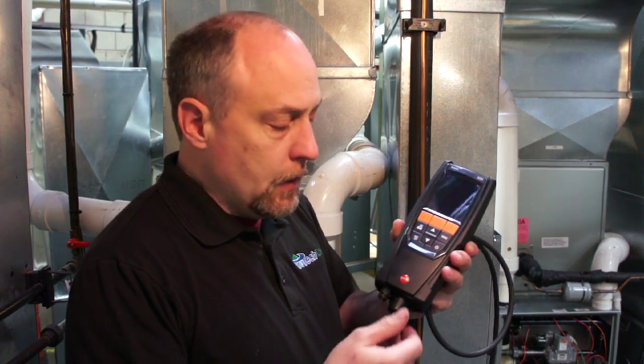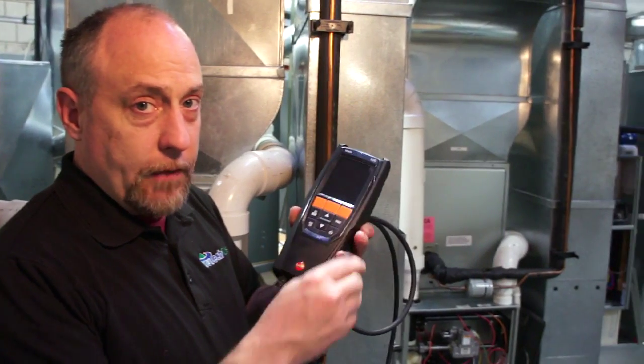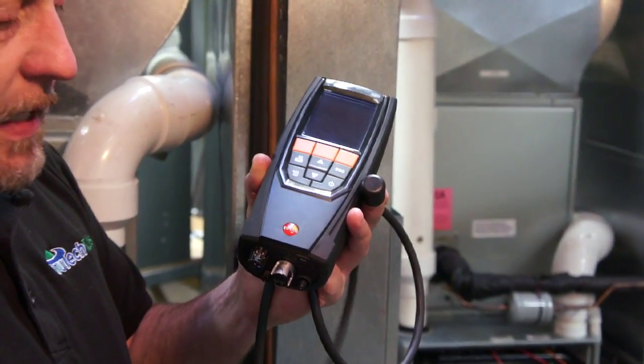Alright, before we power up the Testo 320, one of the first things we want to do is attach the probe assembly, because the probe assembly is used for the initial zeroing of the instrument. It's going to measure the stack temperature with the stack thermocouple. So first thing I want to do is pull the dust cover off the bottom of the instrument. Once I get that dust cover off, I need to attach the probe assembly to the bottom of the instrument itself.